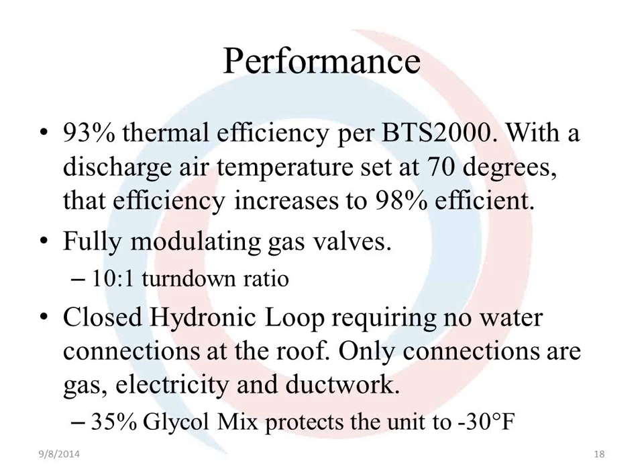The gas valve is fully modulating. There's two boilers, so you have a 5-to-1 turn-down ratio on both, or a 10-to-1. And I'd like to make sure that you realize that the 35% glycol mixture protects the unit down to minus 30.